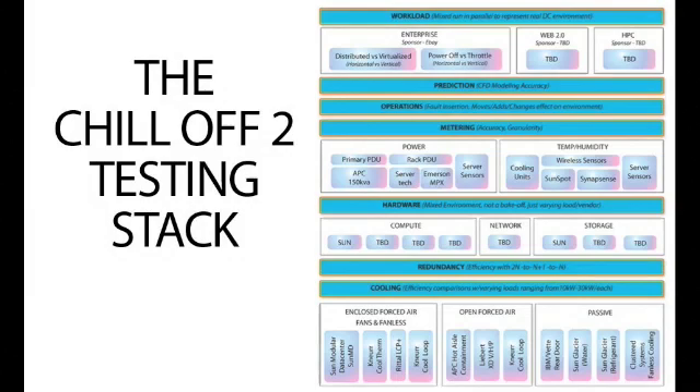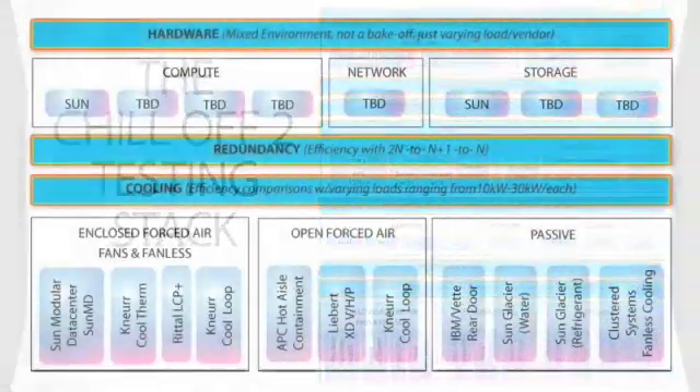Last year we tested cooling efficiency. For Chill-Off 2, we created a stack around the effort covering different vendor categories. At the bottom are cooling solutions, split into three categories. The first is enclosed forced air — fans and fanless — including a Sun container, the Kneurr Cool Therm, Rittal's LCP Plus, and the Kneurr Cool Loop. These products are contained within their own sealed box with their own cooling solution. We want to test them with server fans in place, and then remove the server fans to let the enclosed unit's cooling devices handle everything.